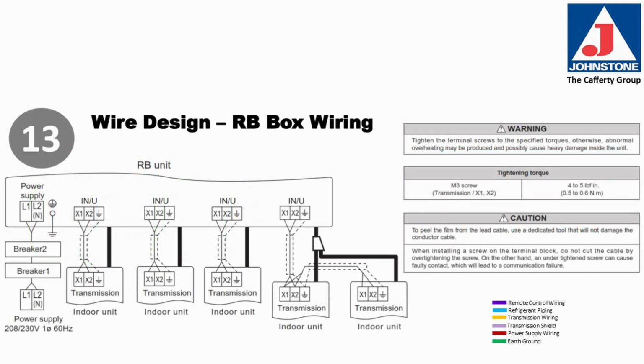Wire design for the refrigerant branch box wiring. You see in the diagram below that there are power connections and transmission or communication connections on these units. Tighten the terminal screws to the specified torque shown in the manual. Otherwise, it may overheat and possibly cause damage to the inside of the unit. Torque specs: tightening torque for the M3 screws on the transmission line should be 4 to 5 inch-pounds of torque.